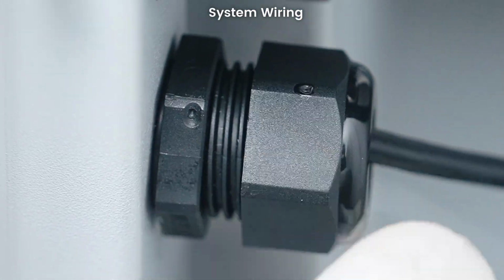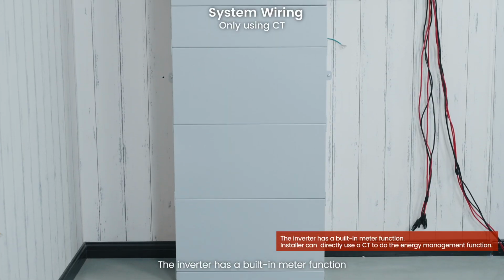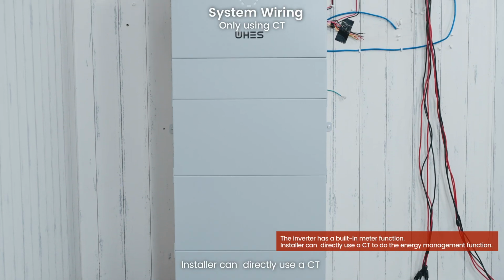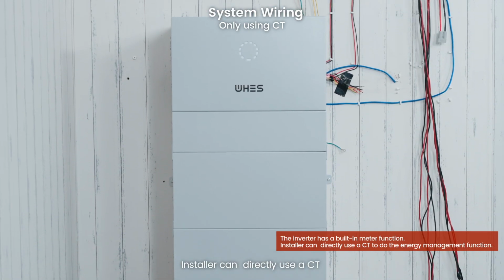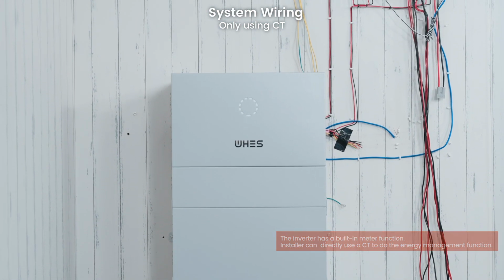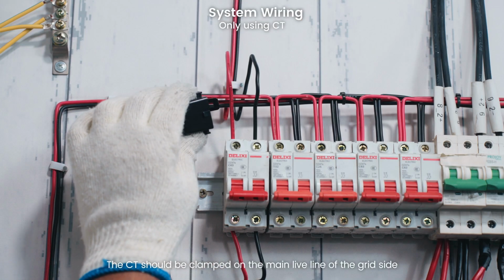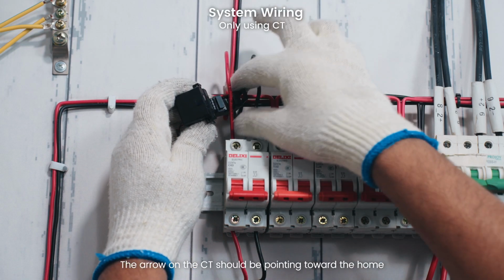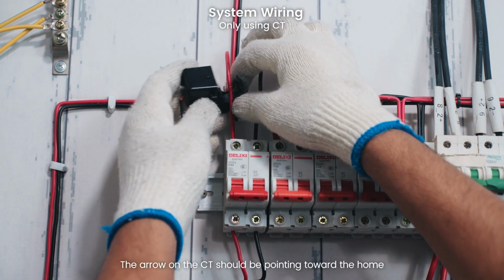Tighten the nut. The inverter has a built-in meter function. Installer can directly use a CT to do the energy management function. The CT should be clamped on the main live line of the grid side. The arrow on the CT should be pointing toward the home.